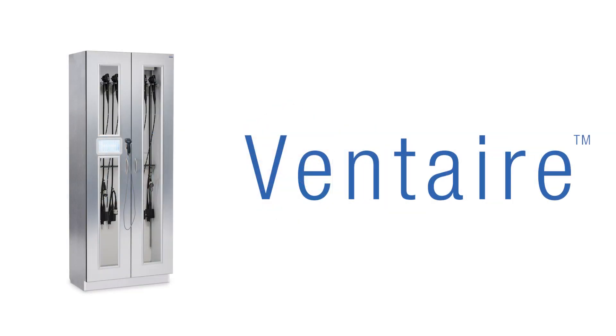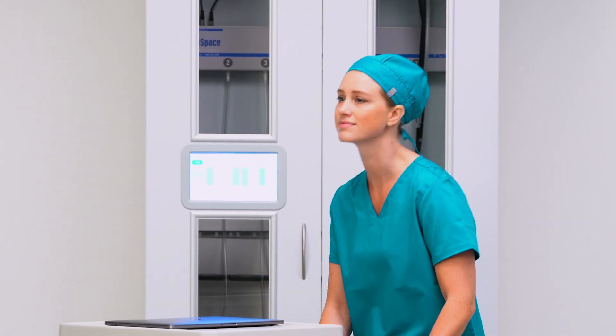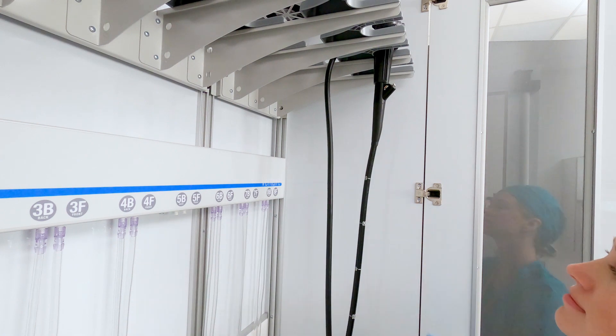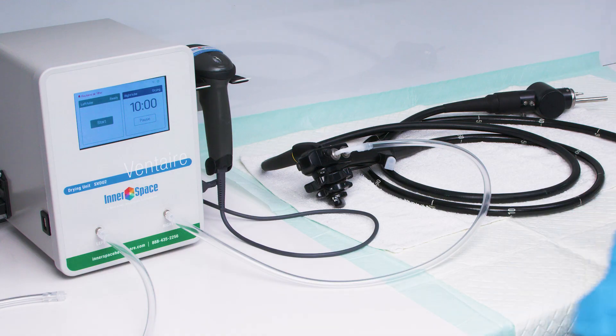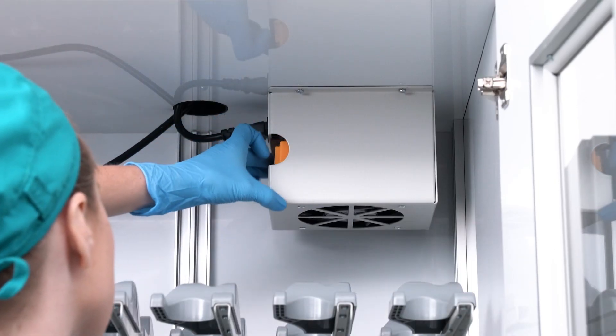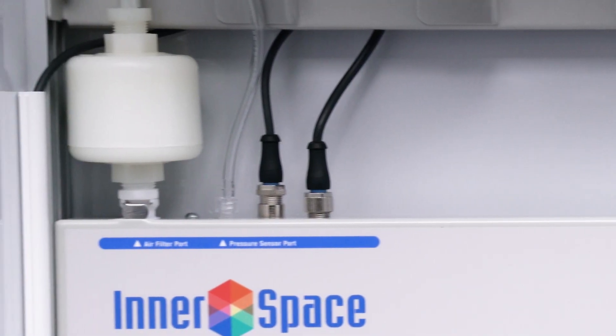The Ventaire system from Innerspace includes products that assist endoscopy staff in the safe and thorough drying, tracking, and storage of reprocessed scopes, including Ventaire drying and tracking cabinets and Ventaire drying units. Both products provide consistent and continuous delivery of HEPA-filtered, pressurized air into endoscope channels to keep scopes dry.